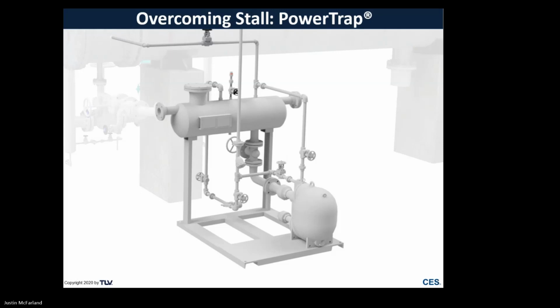Of what happens. So our process heater is generating condensate. That's going to gravity drain down to a reservoir, down through some extra piping, and begin filling up our power trap device right there. During startup, or let's say there's air, we're going to be displacing vapors, and the air is going to be pushed out the air vent. If it's in a positive differential pressure scenario, then this will act just like a steam trap. And the moment that we have negative differential pressure, well, then condensate begins to back up and we're in trouble. Wait, no, we're not in trouble.